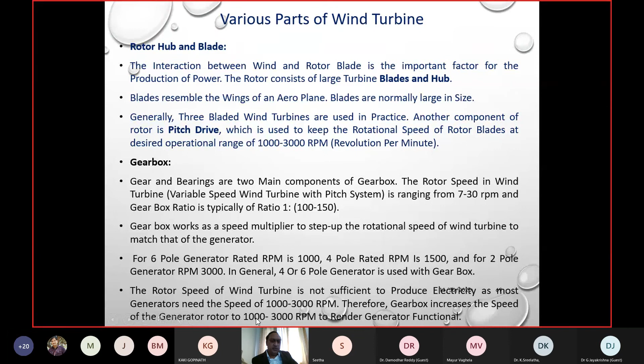So the gearbox is a speed amplifier. Okay. The 6-pole generator rated RPM is 1000, 4-pole is 1500, 2-pole is 3000. In general 4 or 6-pole is used, to have the lower speed with a gearbox. The rotor speed of the wind turbine is not sufficient to produce electricity, as most generators need a speed of 1000 to 3000 RPM. That is why there is a gearbox. Therefore the gearbox increases the speed of the generator rotor to 1000 to 3000 to render the generator functional.